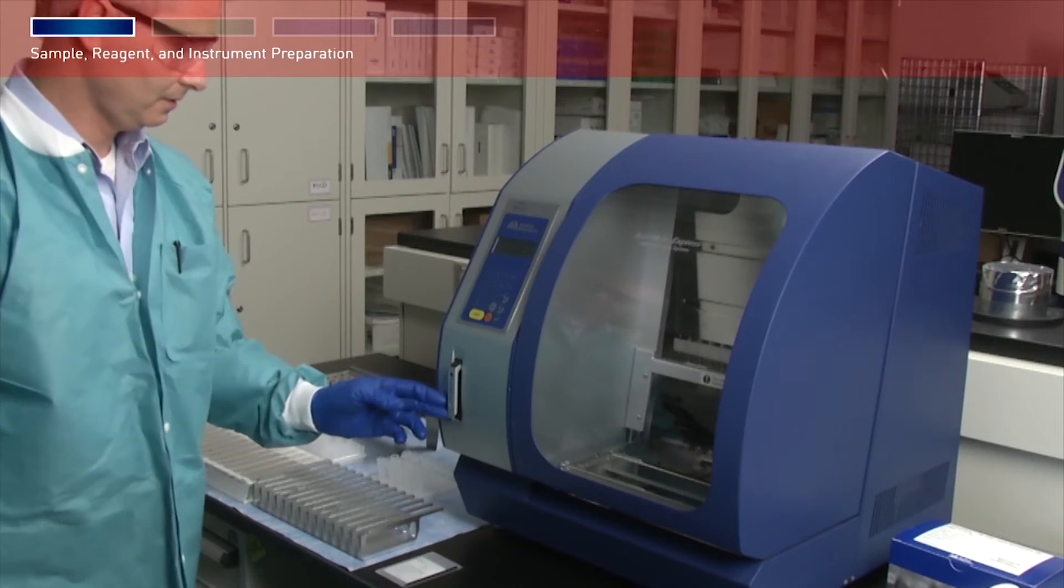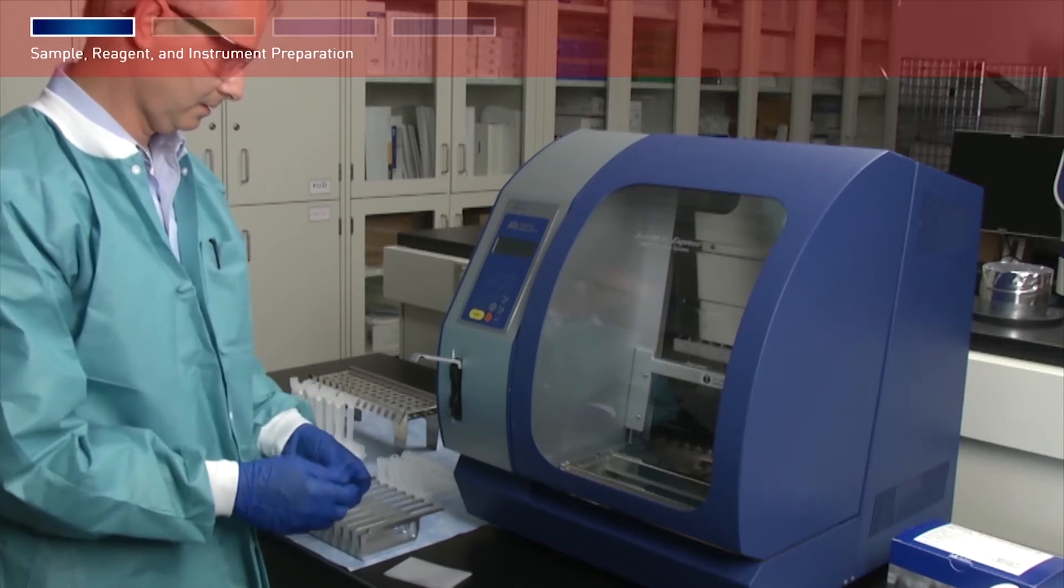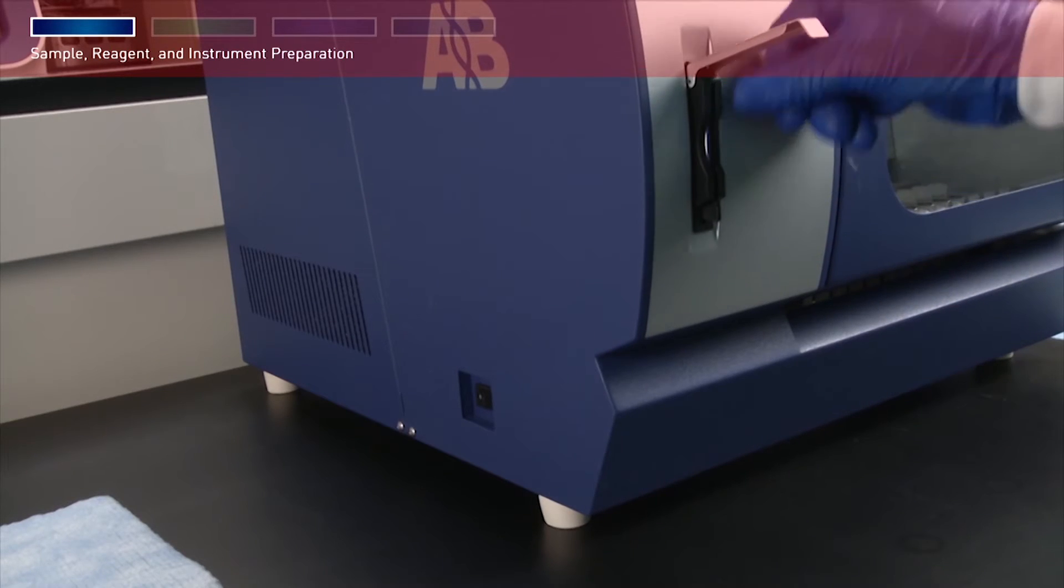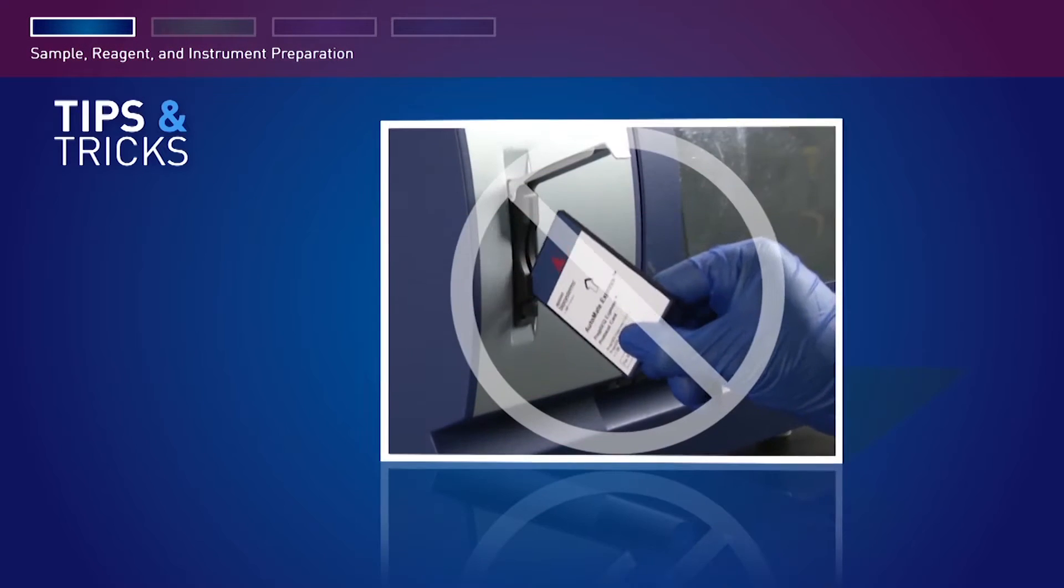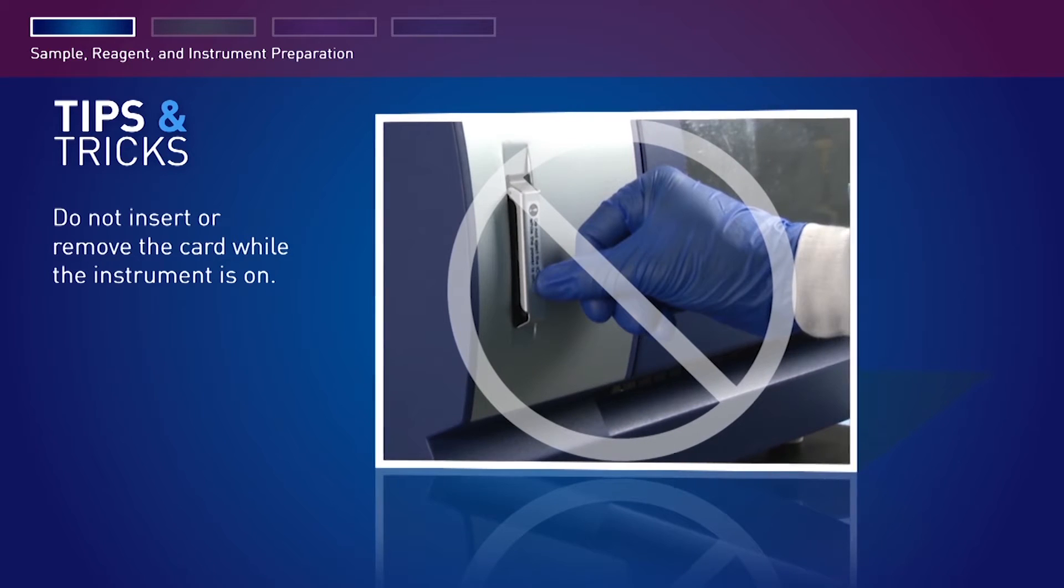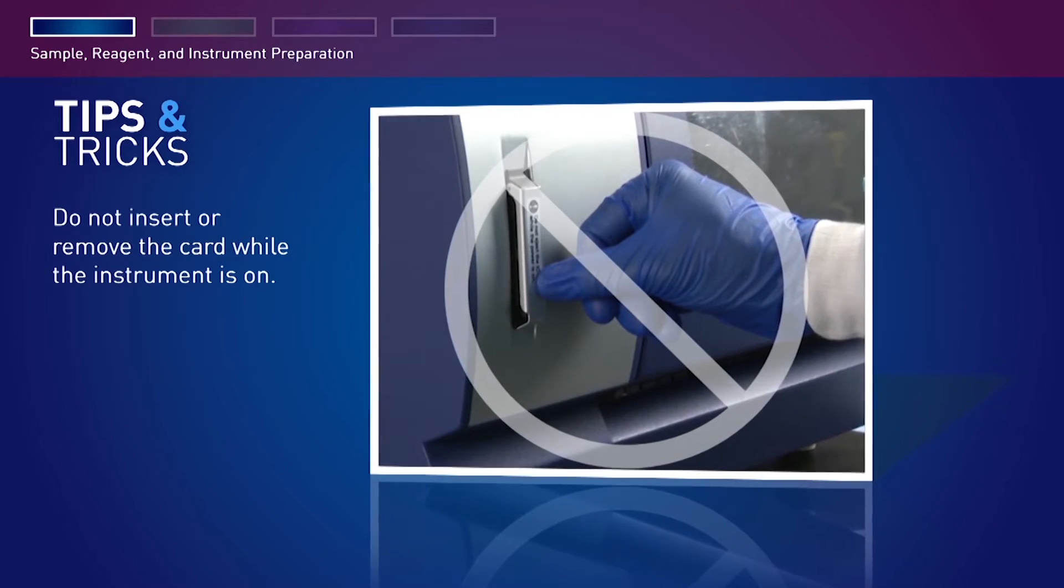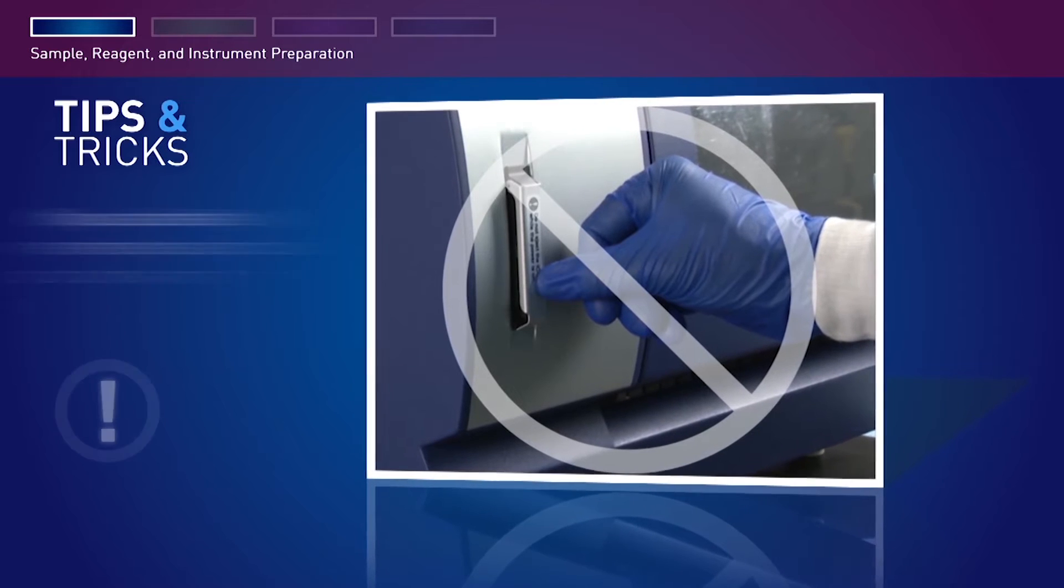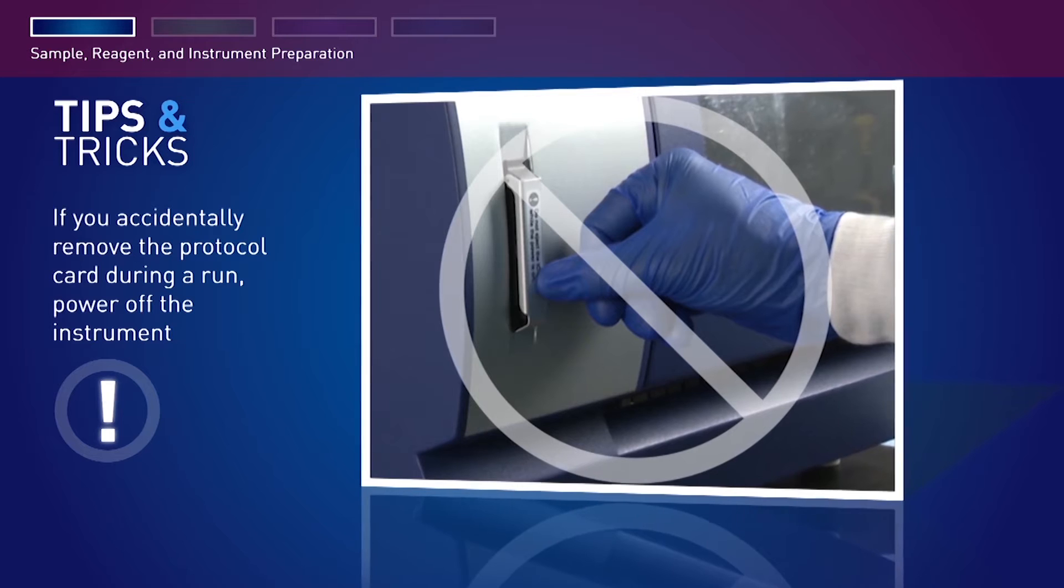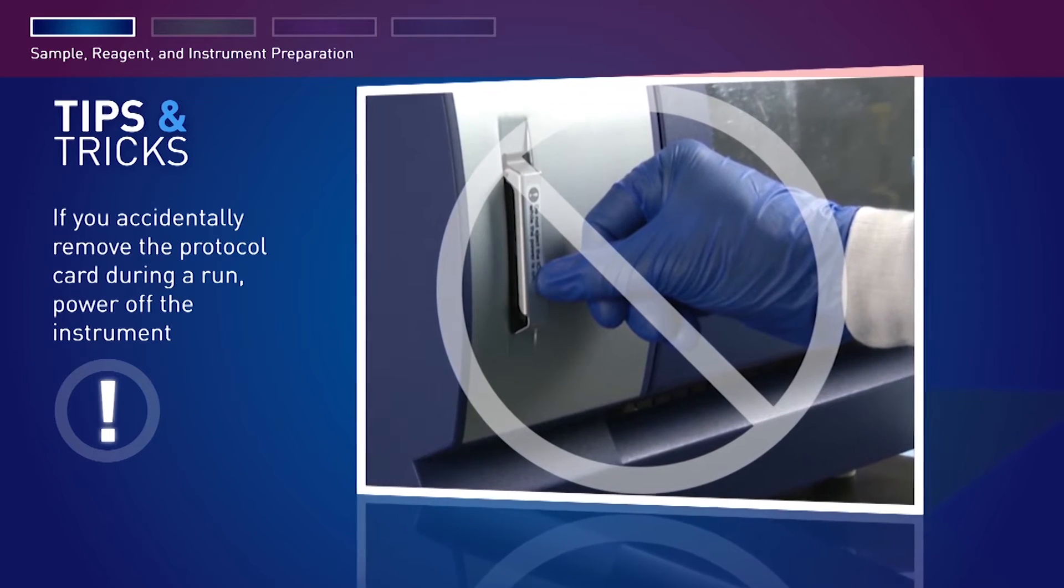Open the card slot and insert the PrepSeek Express kit protocol card in the slot with the arrow pointing toward the instrument and the card label facing left, then close the card slot. Do not remove or insert the protocol card while the instrument is on. Removing the card stops the run and may cause instrument data file loss. If you accidentally remove the protocol card during a run, power off the instrument immediately to minimize potential for instrument data file loss.